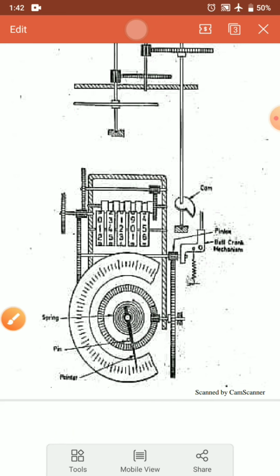Now from 1 p.m. to 1:30 p.m., as we have said, the demand was 120. This is the 120 position. The pointer will move to 120, and again the pin's position is moved. That is, it is shifted 20 units to the top. Now looking at the position of the pin, I can clearly make out what was the maximum energy that was consumed.